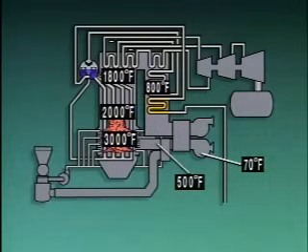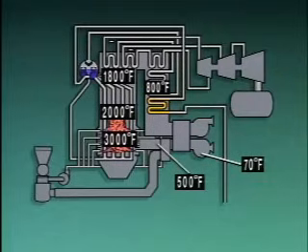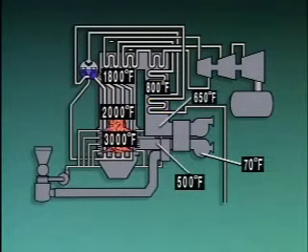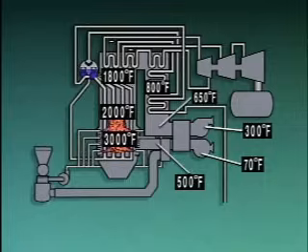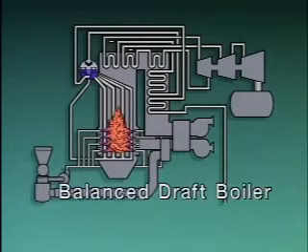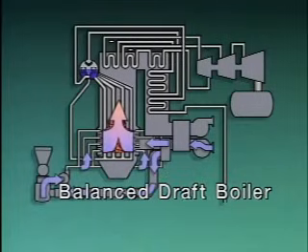The economizer uses heat from the combustion gases to raise the temperature of feed water on its way to the boiler. Feed water flows through the tubes of the economizer and the combustion gases flow around the tubes. When they leave the economizer, the combustion gases have cooled to about 650 degrees Fahrenheit. The gases then pass through the air preheater, where their temperature drops another 350 degrees. Finally, the gases flow through an induced draft fan and leave the boiler at about 300 degrees. This is a balanced draft boiler because it has both a forced draft fan, which pushes air in, and an induced draft fan, which pulls combustion gases from the furnace.